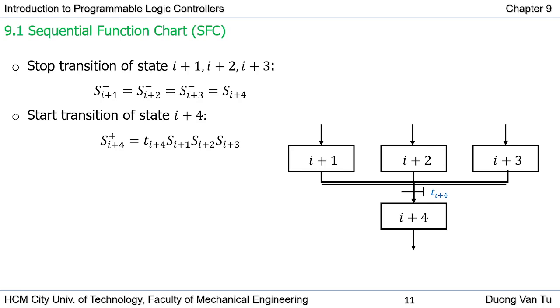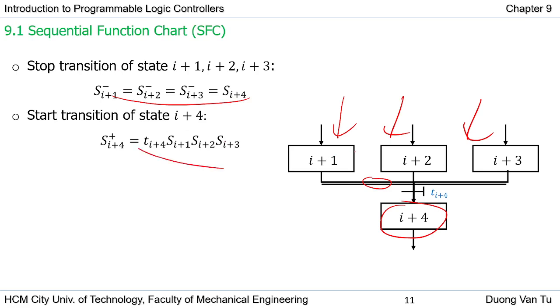For the simultaneous convergence — shown with a double line — all three branches are implemented simultaneously before converging to step I-plus-four. The stop transition is the same for each branch, but the starting transition for state I-plus-four is different: we need all three conditions — step I-plus-one, step I-plus-two, and step I-plus-three to be active — AND transition TI-plus-four to be true, then we can switch to step I-plus-four.